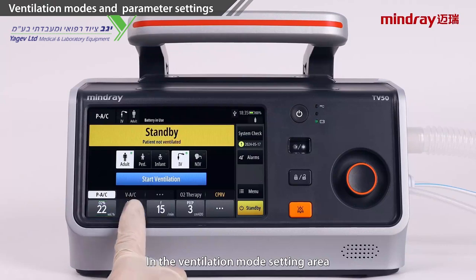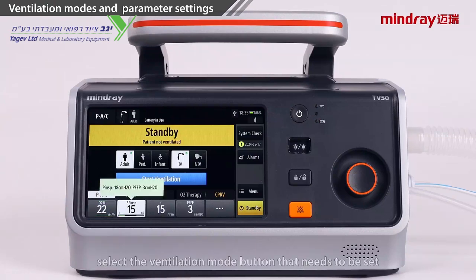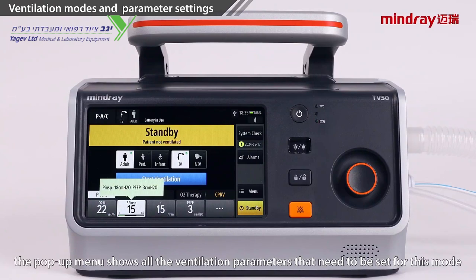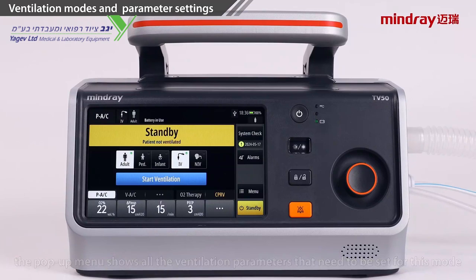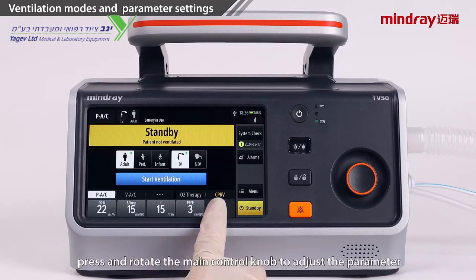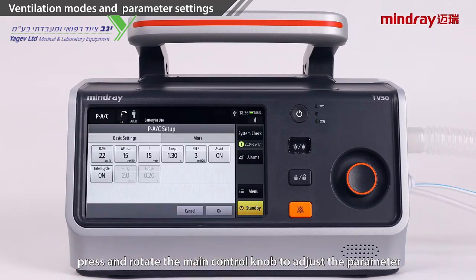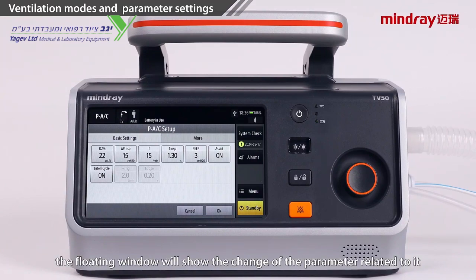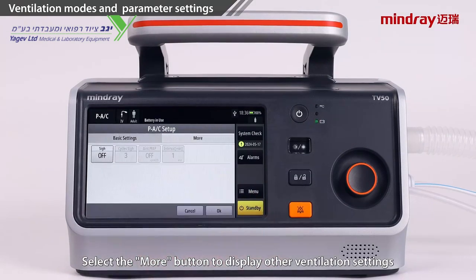In the ventilation mode setting area, select the ventilation mode button that needs to be set. The pop-up menu shows all the ventilation parameters that need to be set for this mode. Select a parameter, press and rotate the main control knob to adjust the parameter. When adjusting the parameter, the floating window will show the change of the parameters related to it. Press the main control knob again to confirm the parameter. Select the More button to display other ventilation settings.